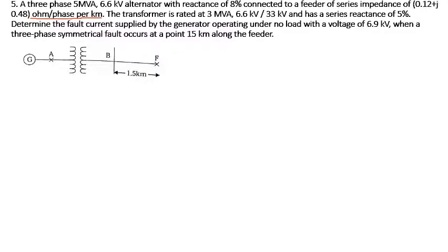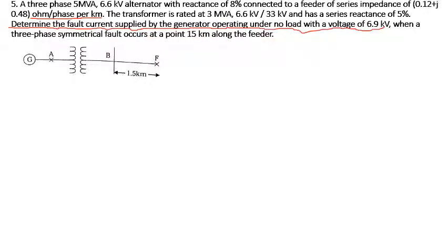We have to determine the fault current supplied by the generator operating under no load with a voltage of 6.9 kV. You need to be very careful because it is working at 6.6 kV but there is a changed voltage of 6.9 kV. There is a three-phase fault which is going to occur at 15 kilometers along the feeder.